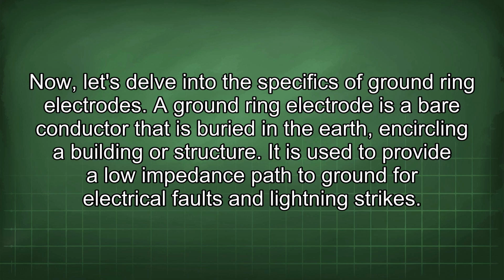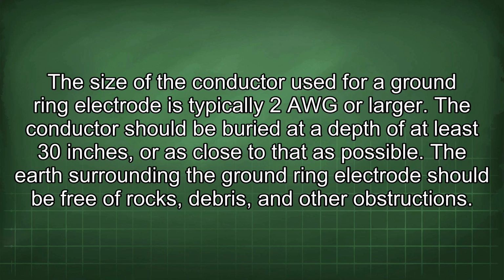A ground ring electrode is a bare conductor that is buried in the earth, encircling a building or structure. It is used to provide a low impedance path to ground for electrical faults and lightning strikes. The size of the conductor used for a ground ring electrode is typically 2 AWG or larger. The conductor should be buried at a depth of at least 30 inches, or as close to that as possible. The earth surrounding the ground ring electrode should be free of rocks, debris, and other obstructions.